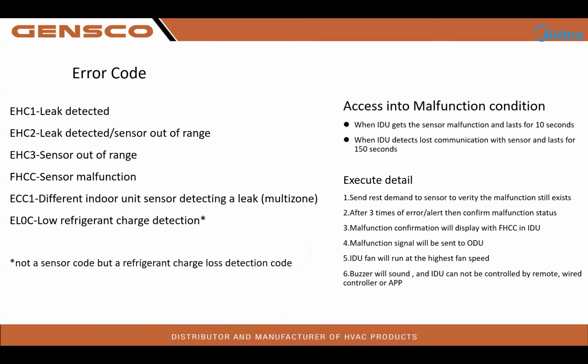Now, in the event that you get an FHCC, sensor malfunction, you will need to double check to make sure that you have the sensor plugged into the black CN8 port. If it is plugged into the red port, it's not going to recognize it, and it'll give you the FHCC. It doesn't mean that the sensor is bad. It just means that there is a malfunction on it finding itself. And make sure that SW5 is in the off position. SW5 in the off position, it's a little red single dip switch. And make sure your refrigerant leak detector is plugged into the black CN8 port.